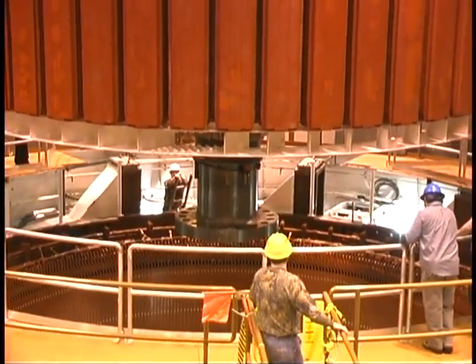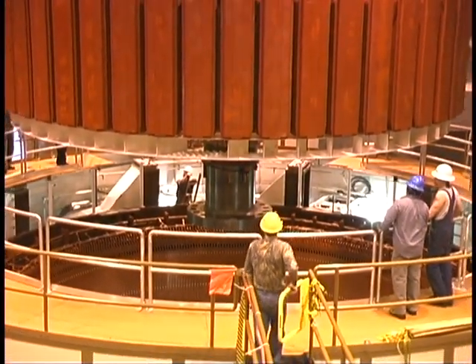Probably on average every 10 to 15 years one would need to be pulled apart. Orrin Wilson, Ross generation supervisor, says it's all part of keeping the machines reliable. We went through some rebuilds in the 90s where they replaced runners — the turbine part — on some equipment and did upgrades to others. Then they went through and cleaned things up and checked them out. Based on those inspections is where they made the determination to do this generator rewind.